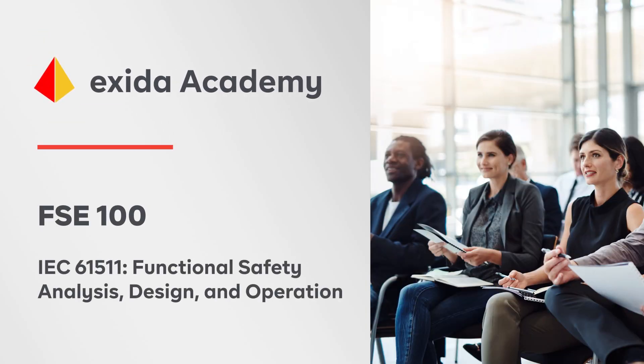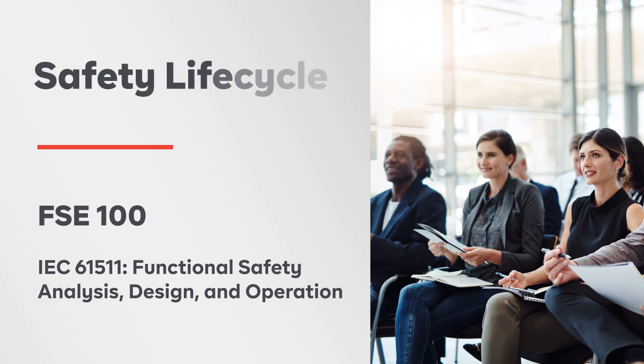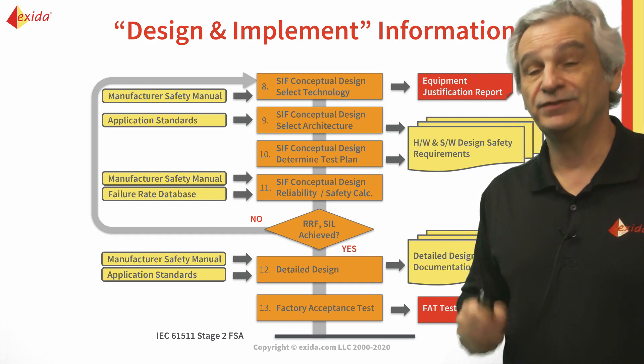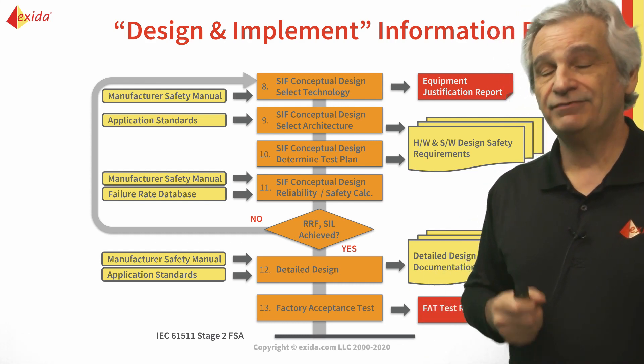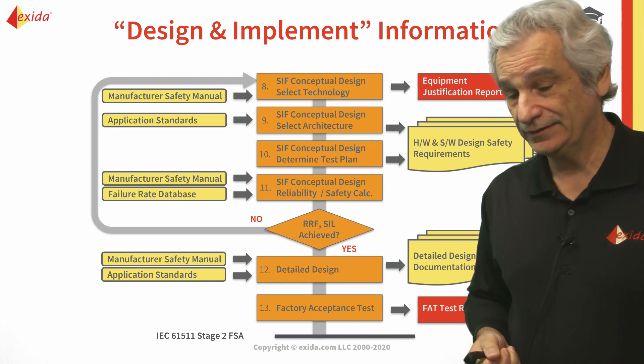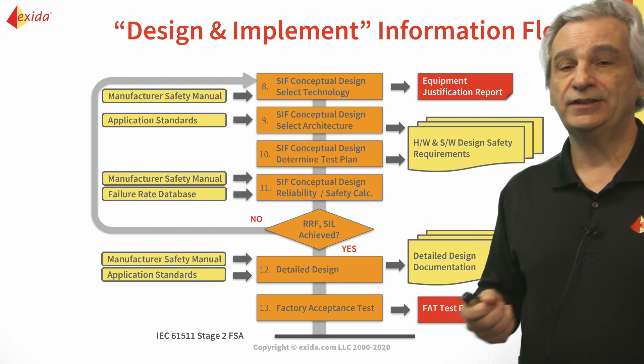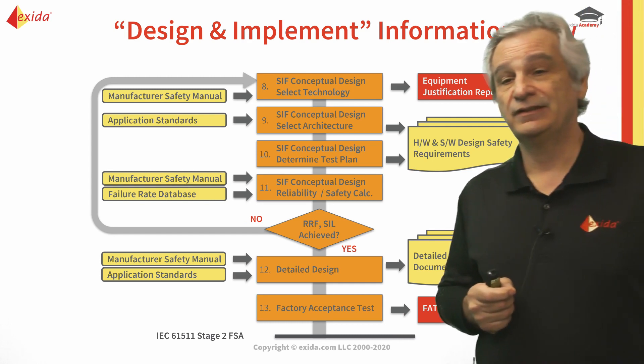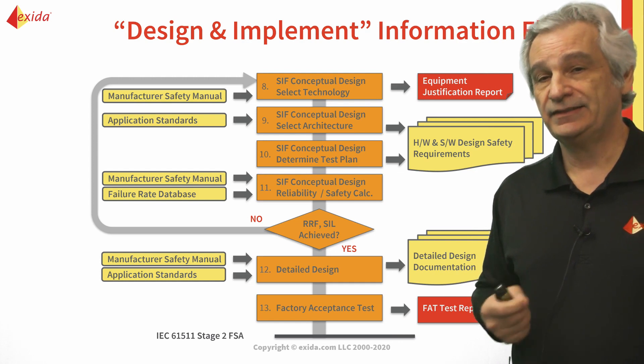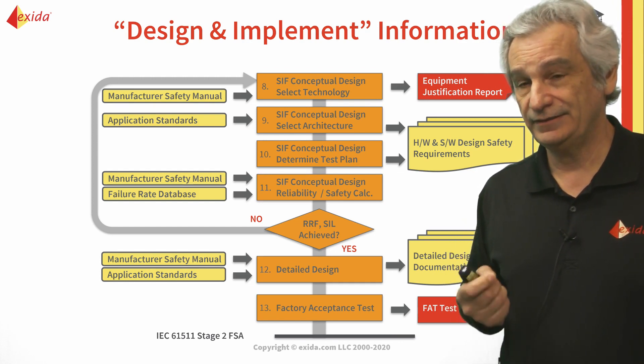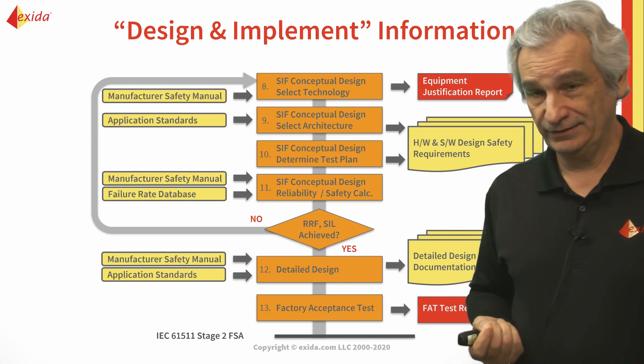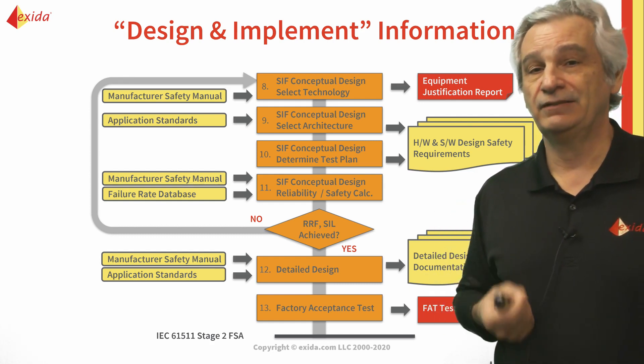The next phase of the lifecycle is design and implementation. In this phase, we take our initial SRS and do some conceptual design — thinking about what technology and devices we're going to use. We have to create a justification for the use of those devices. IEC 61511 allows us two methods only for selection of equipment: one is to use IEC 61508 certified devices for the relevant SIL, issued by an accredited agency, so the safety numbers and failure rates are reliable.